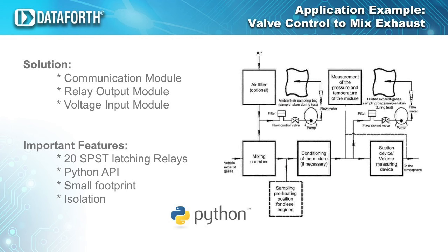Output to bus isolation is a robust 1500 volts RMS, and each individual channel is protected up to 150 volt RMS continuous overload in case of inadvertent wiring errors. 150 volt RMS channel-to-channel isolation gives the module the ability to control equipment with or without common mode signal grounds or different pieces of equipment with multiple reference potentials. Like all MAQ20 modules, the MAQ20 DO Relay 20 is designed for installation in Class 1 Division 2 hazardous locations and has a high level of immunity to environmental noise commonly present in heavy industrial environments.